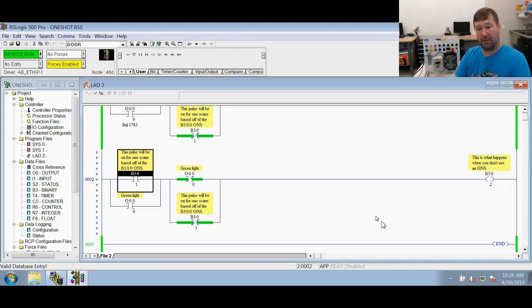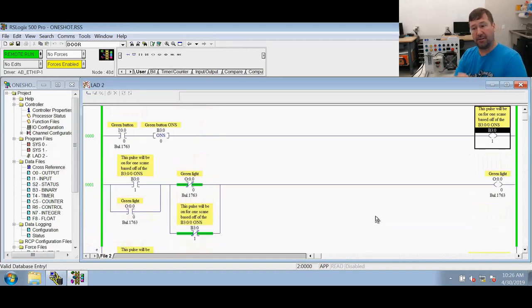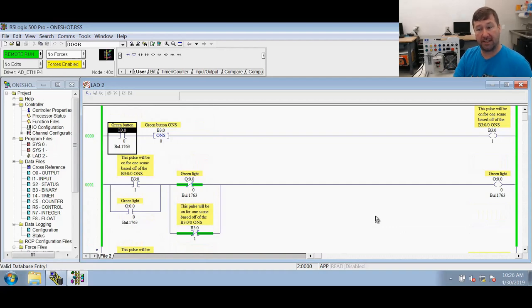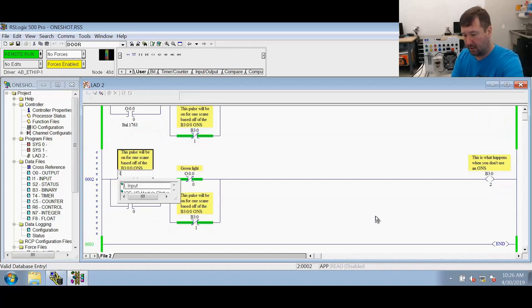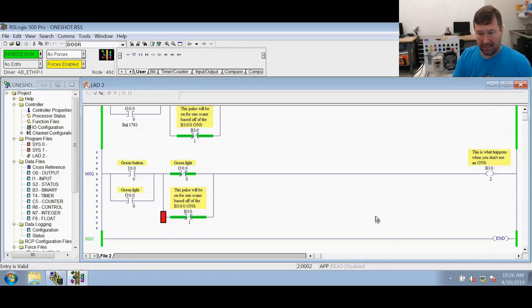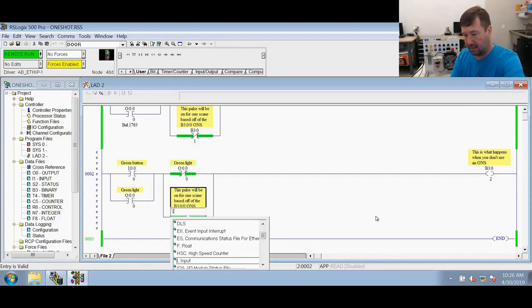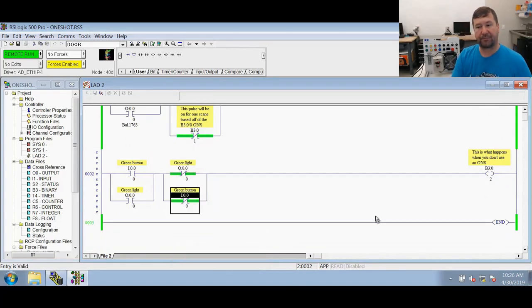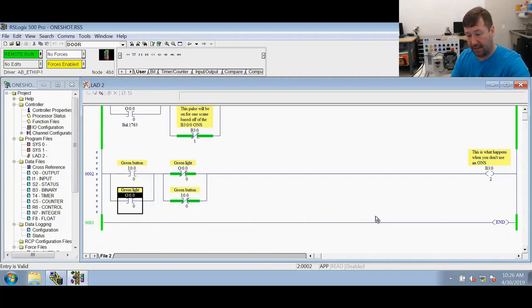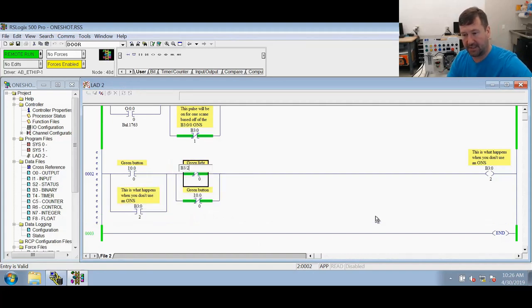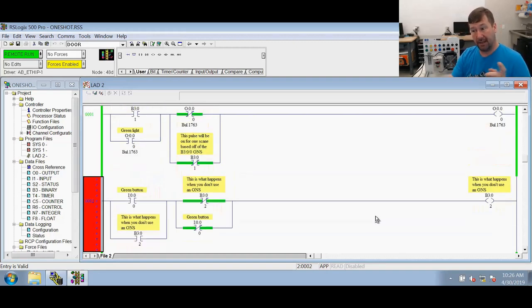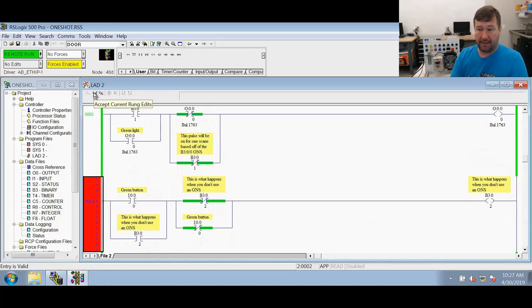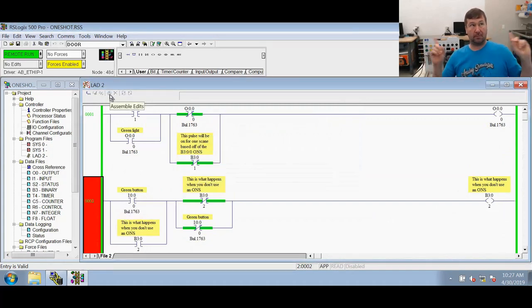We're going to change this program. So this B31 if you recall from rung zero is what we're using with the ONS. We're going to address the green button instead of it. So instead of B3 backslash one we're going to put in I colon zero backslash zero. And then right down here in this lower branch same thing it's going to be I colon zero backslash zero. Now instead of the green light since we're going to this B32 bit we're going to change the green light here also. So B3 backslash two and right here B3 backslash two. So this is the exact same rung as this only without the ONS and please tell me that you did change and you're not using an output instruction here. Accept these edits, test them, and then assemble them.